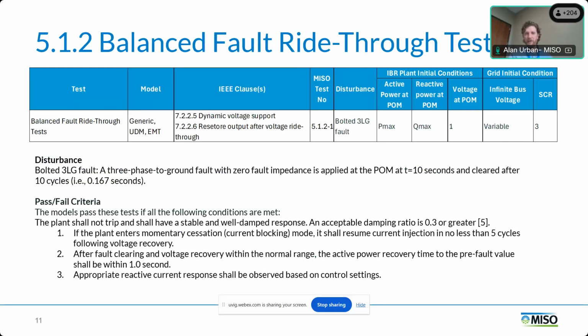We have a balanced fault ride-through test. The main things we're looking for here are that the plant, if it does enter momentary cessation, can resume current injection in no less than 5 cycles once the voltage recovers. Active power recovery should also be appropriate within a second of the fault being cleared.